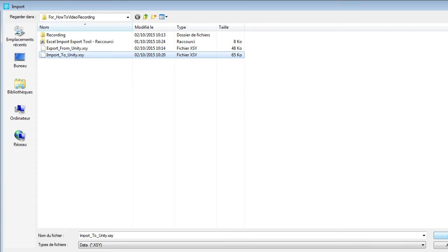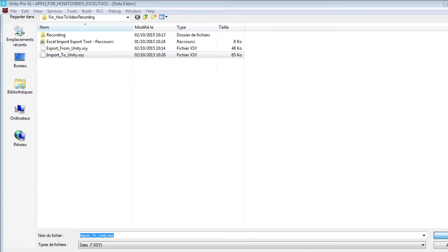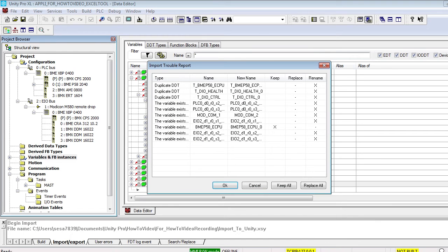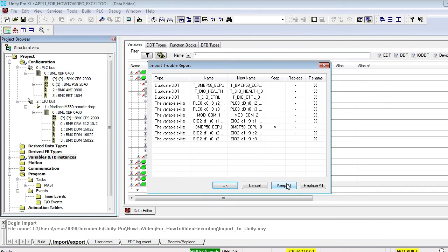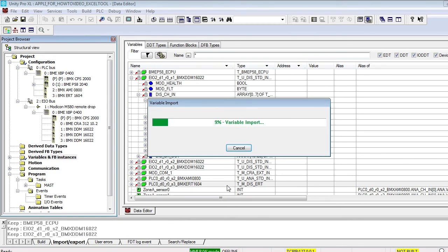Press import in the pop-up window and confirm. When the import trouble report window appears, press the keep all button. You obviously want to keep all device DDTs within your application and just want to create and associate new aliases.